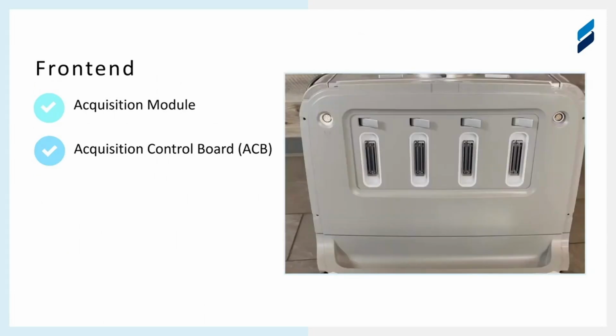All right, we're going to take a look at the front end now and show you the parts and how to deinstall them. Again, reverse the deinstall process to install. Really straightforward, but we're going to be specifically talking about the acquisition module and the acquisition control board. The acquisition control board is technically a front end item, but it is inside the Ebox, so just bear with the system architecture here. There's that gray area. It's physically inside the Ebox, which is technically a back-end item, but its functions are really beamforming and controlling the acquisition module, which technically makes it a front-end board.